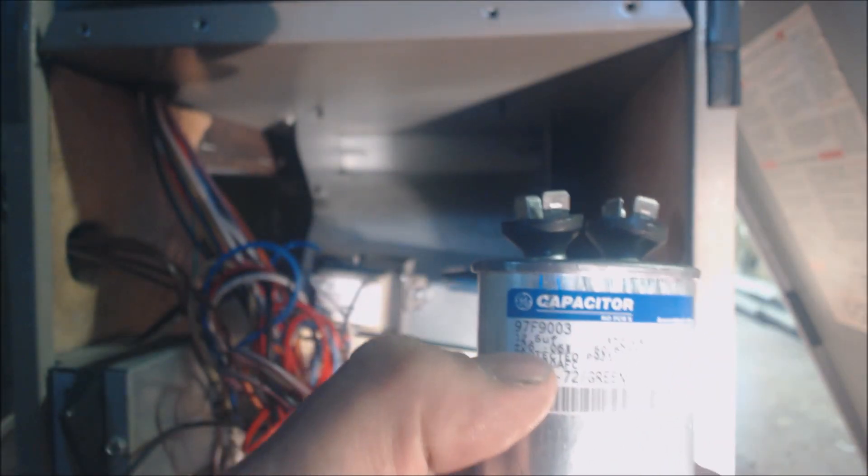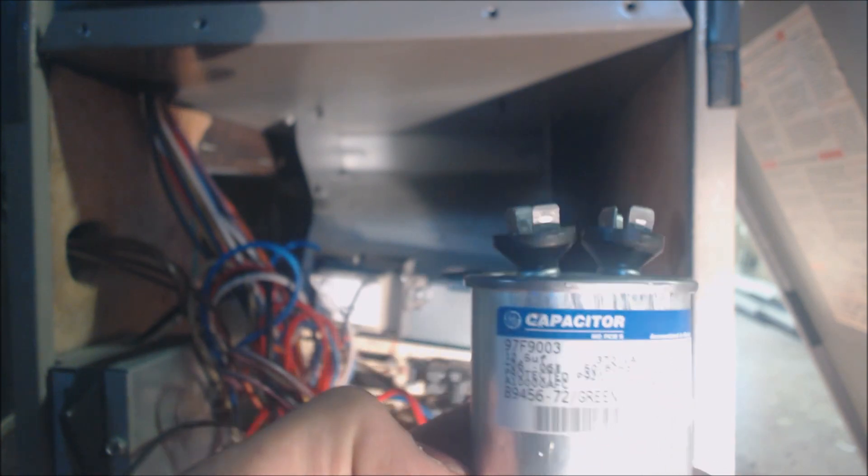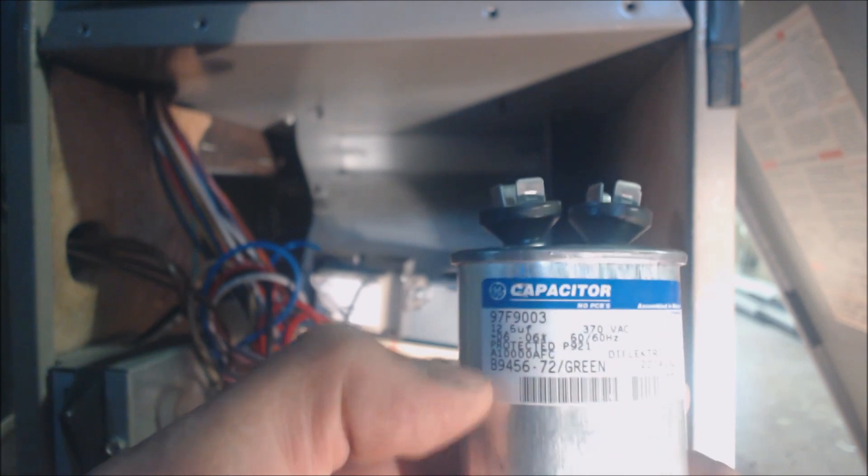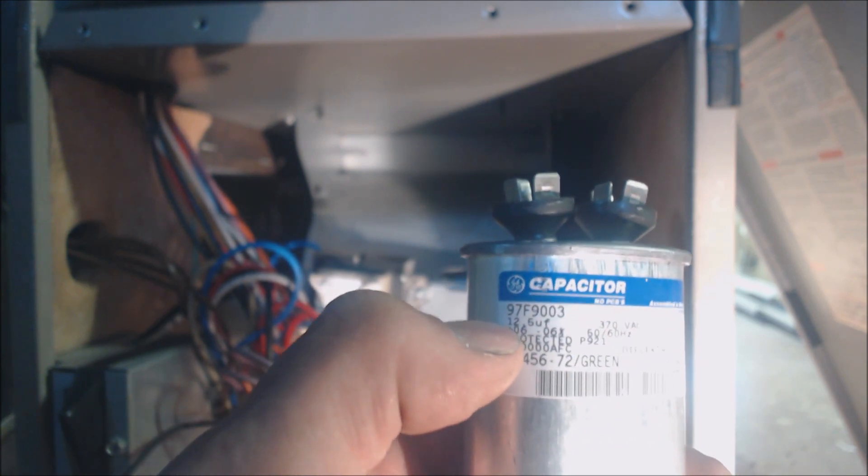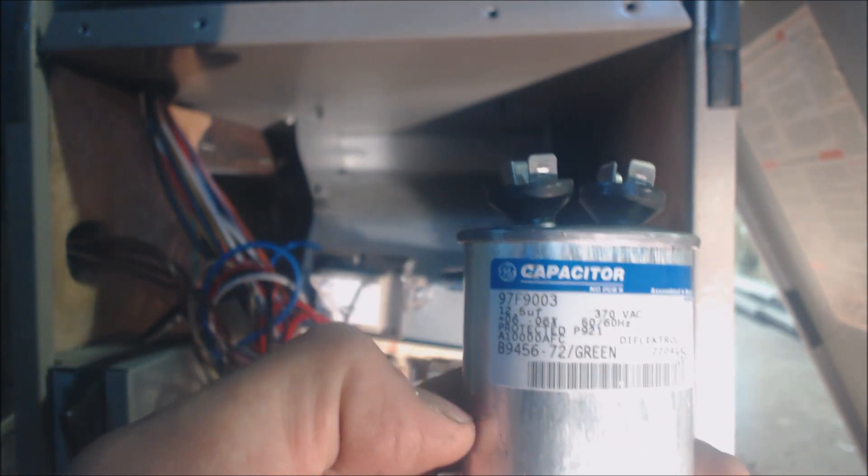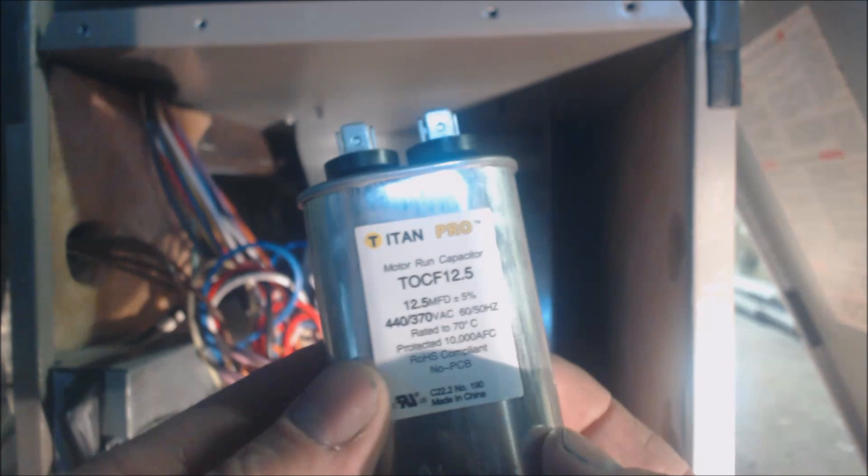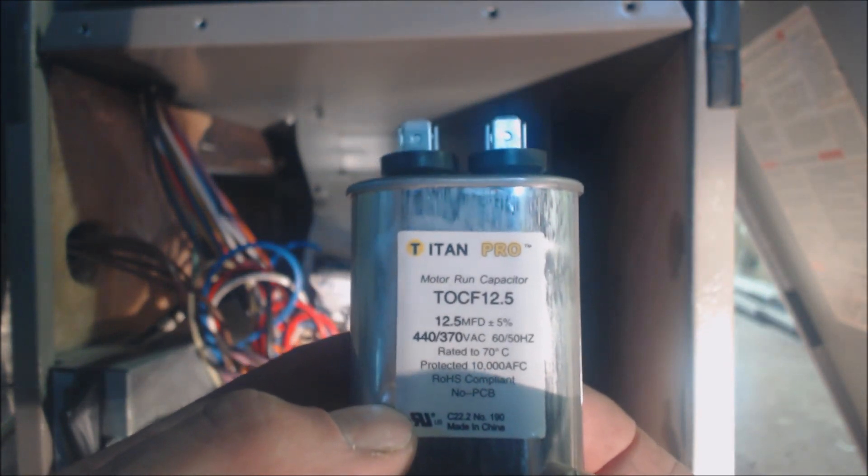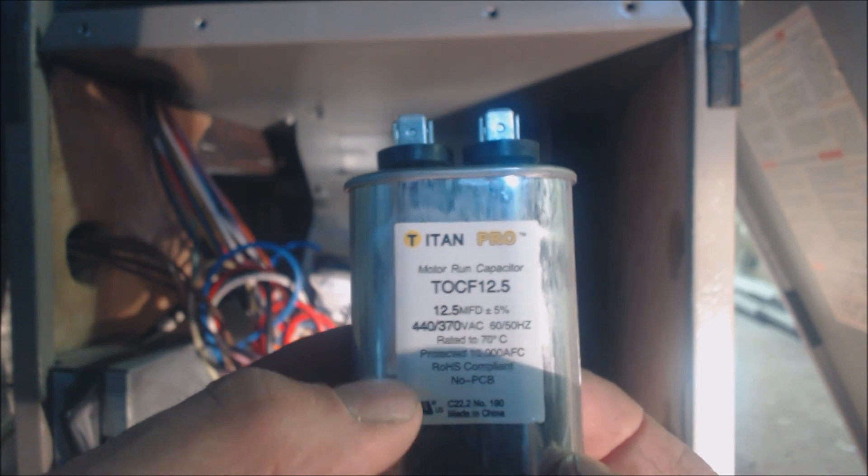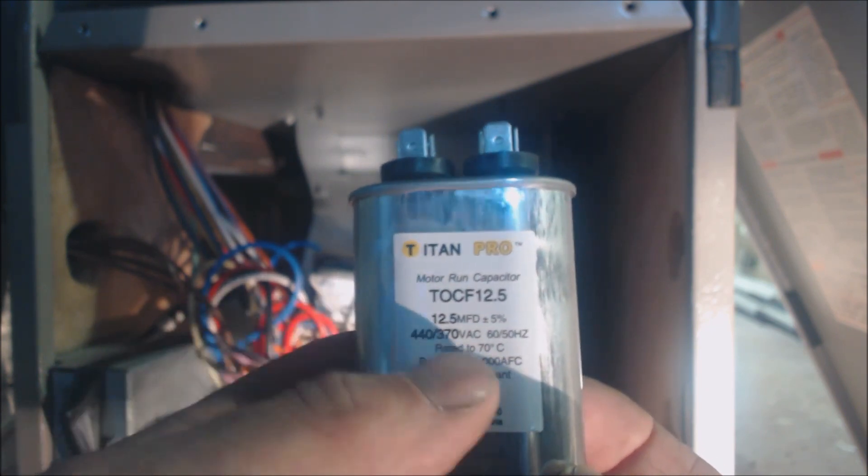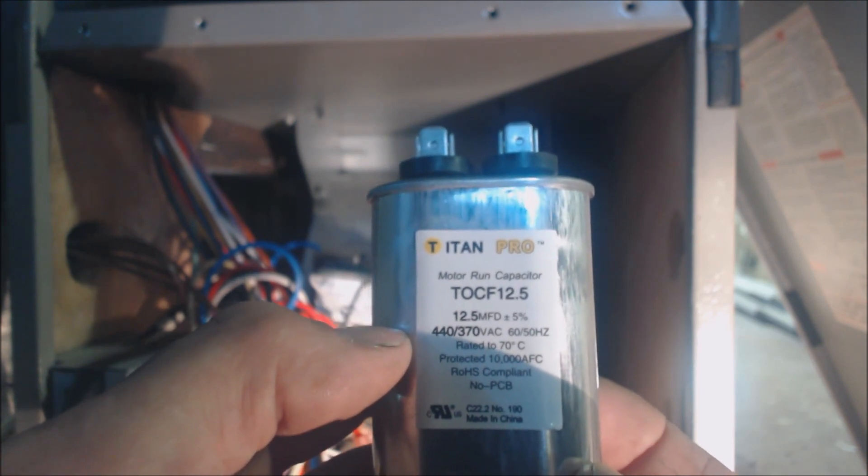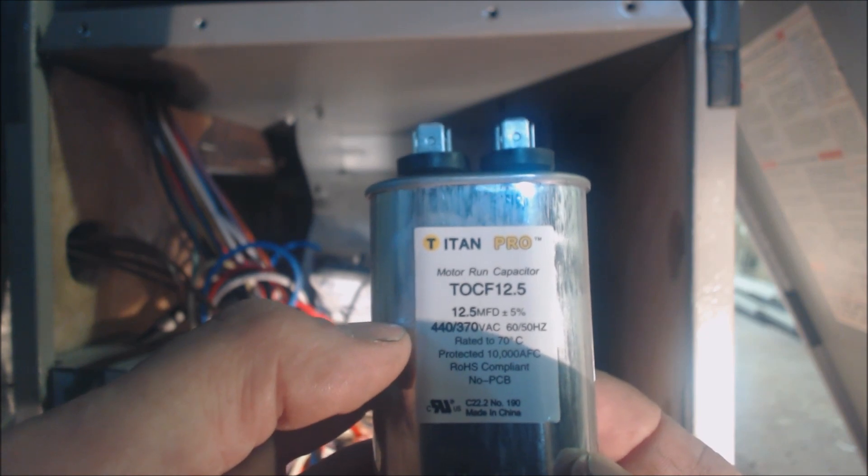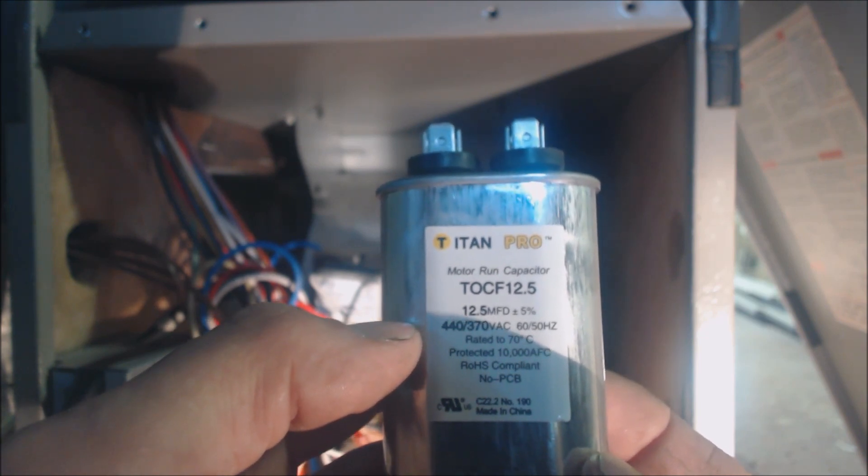This old capacitor is a 12.5 uf, 370 vac, plus or minus six percent. So if you measured anything within six percent of 12.5 it would be good, and we measured absolutely nothing. Here's our new capacitor. That's a 12.5. Got to make sure you replace it with the exact same mfd rating, not manufacturer. This was 370, but 440 is good for either one. Since it's a 370 vac cap, we can replace it with a 440 or 370.